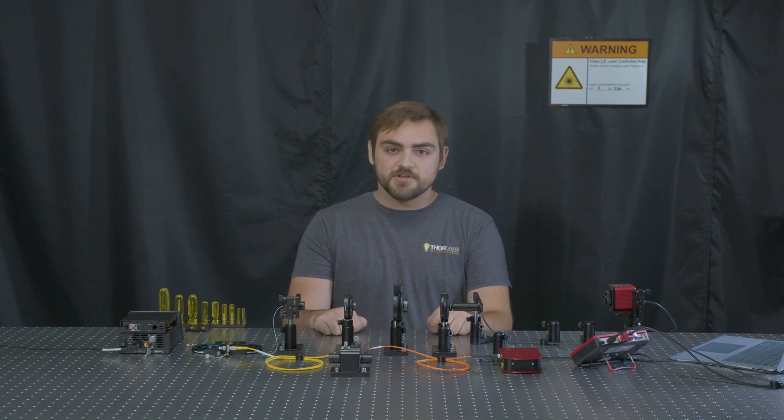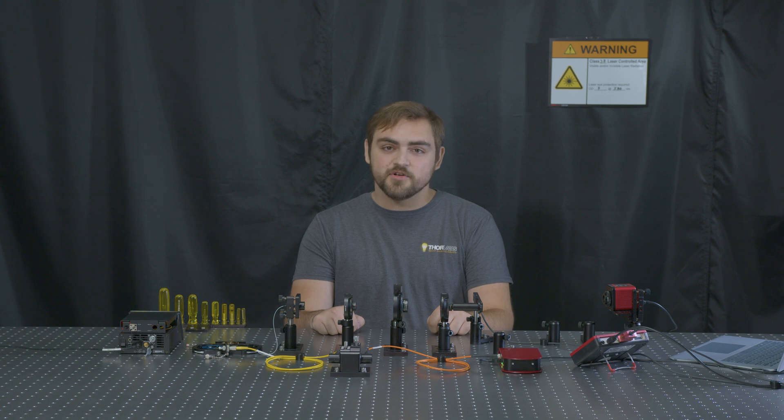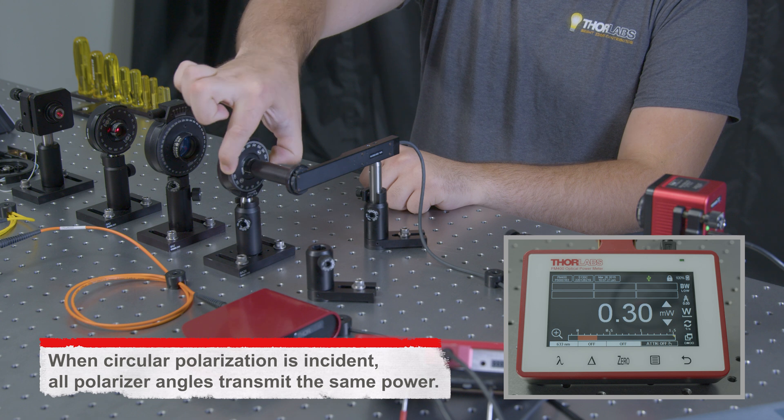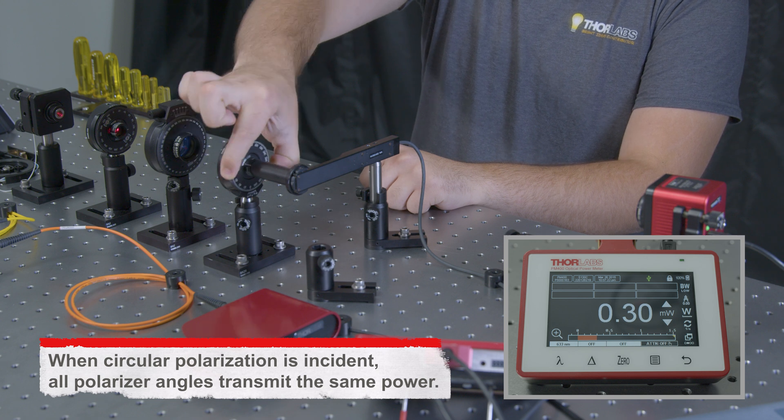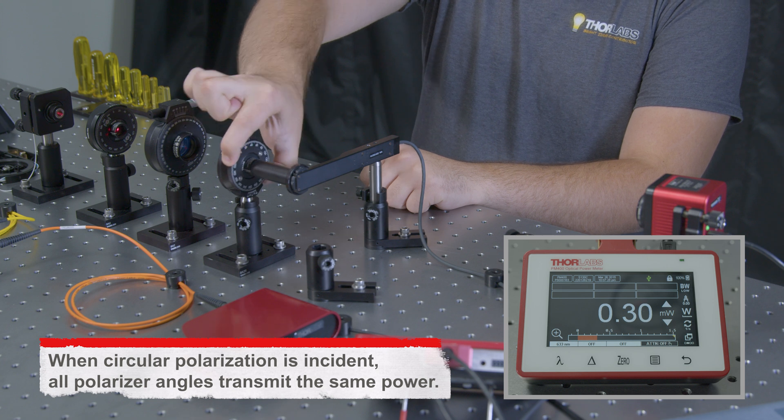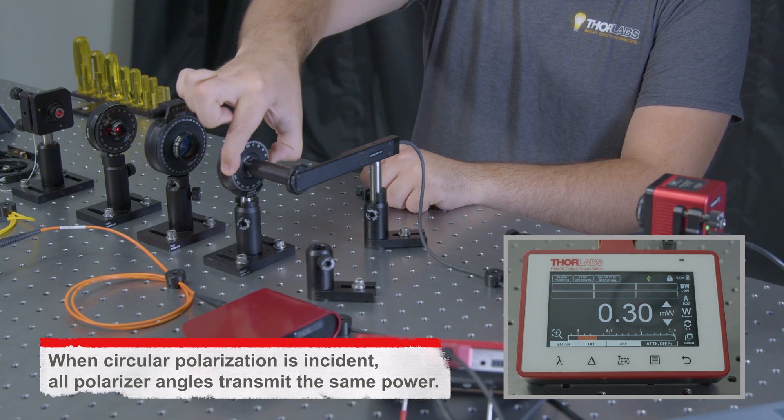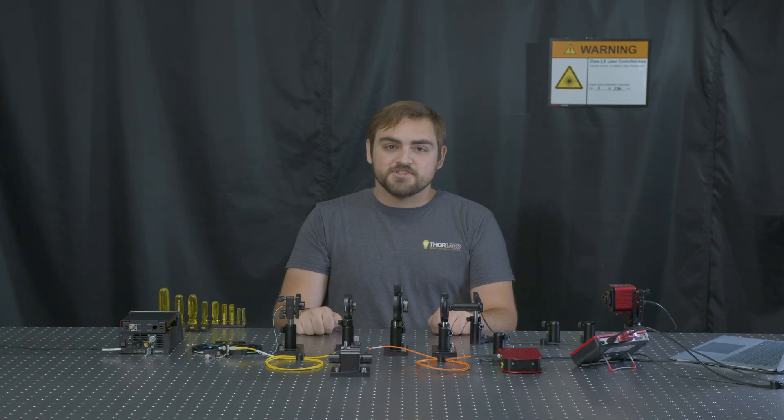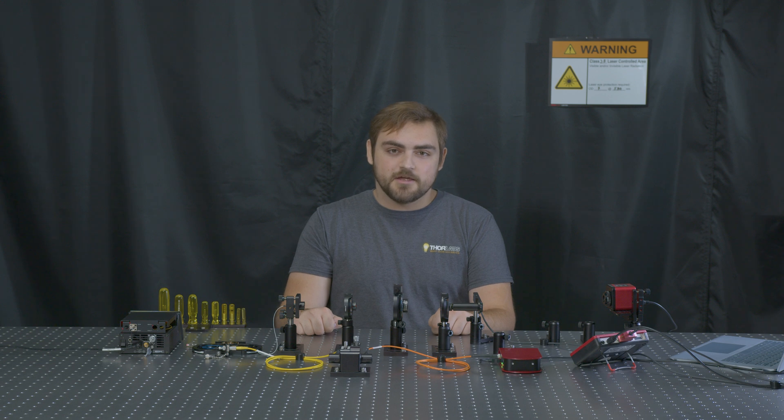Again, we can check this by rotating the analyzing polarizer 360 degrees, where we should see no real power change. If there is still a change in power, we can continue to iteratively tweak the temperature until the power does remain the same. We can confirm our results again by swapping in our polarimeter.